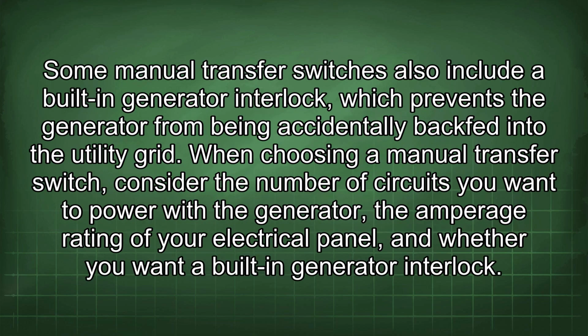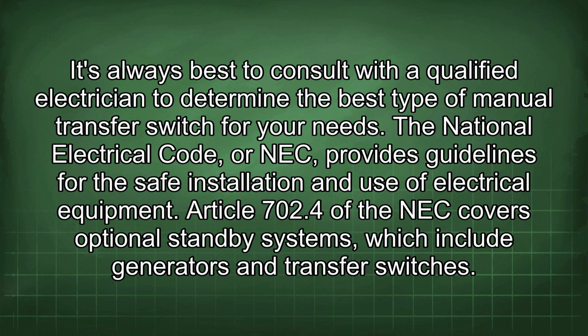Some manual transfer switches also include a built-in generator interlock, which prevents the generator from being accidentally backfed into the utility grid. When choosing a manual transfer switch, consider the number of circuits you want to power with the generator, the amperage rating of your electrical panel, and whether you want a built-in generator interlock. It's always best to consult with a qualified electrician to determine the best type of manual transfer switch for your needs. The National Electrical Code, or NEC, provides guidelines for the safe installation and use of electrical equipment.